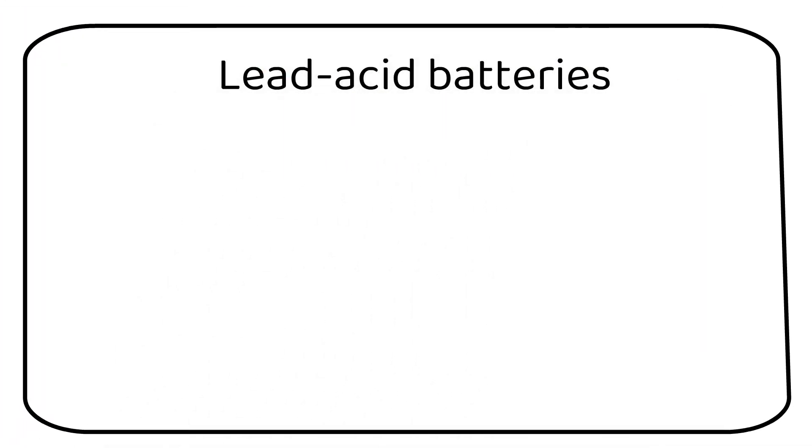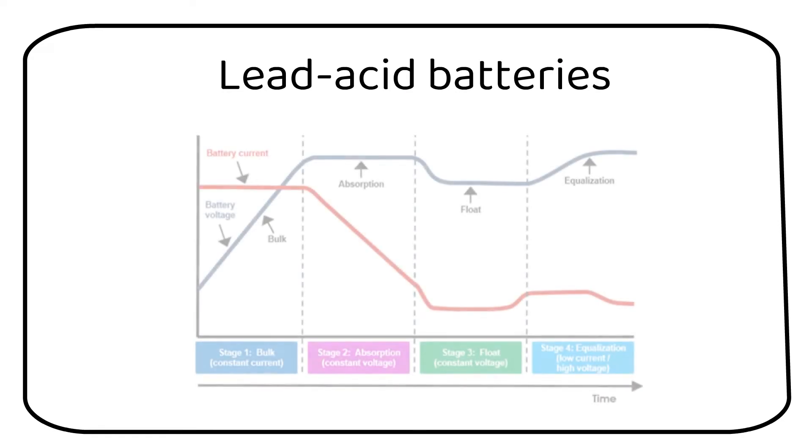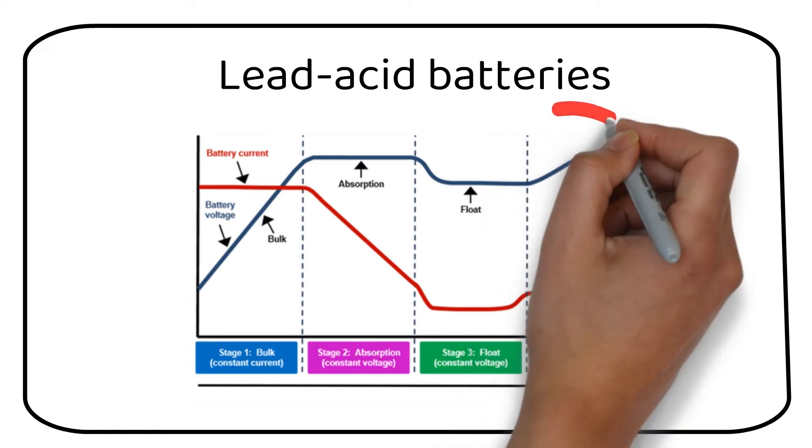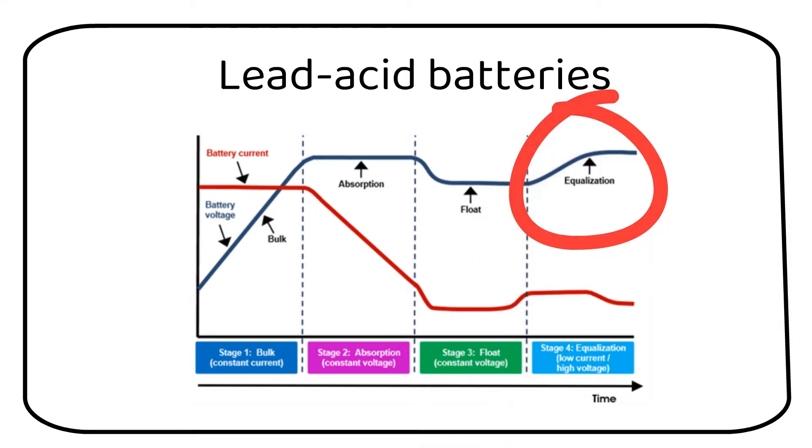Charge controllers for lead-acid batteries have an equalization or anti-sulfation function. This means that the voltage will increase by 10% once per month or multiple times per year depending on the settings. This can be a problem when you have multiple charge controllers. It can lead to overuse of the equalization function. You need to have only one charge controller performing this function.